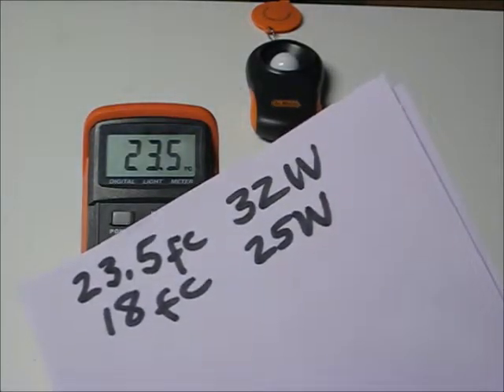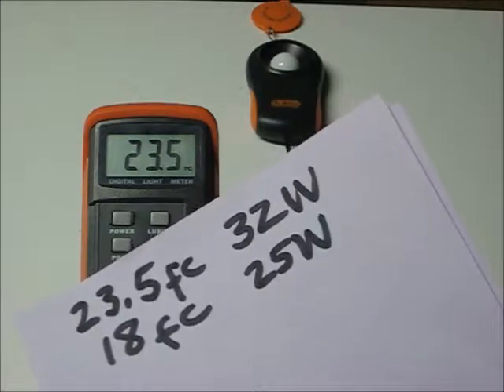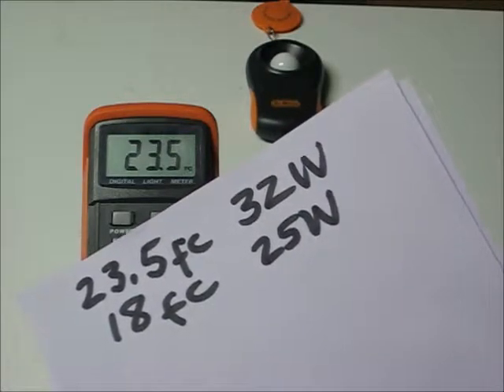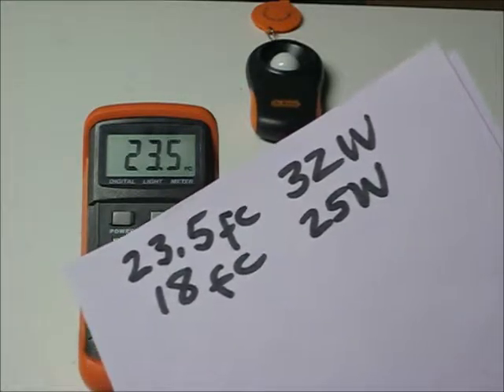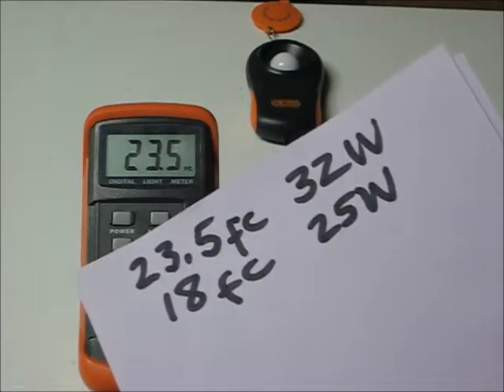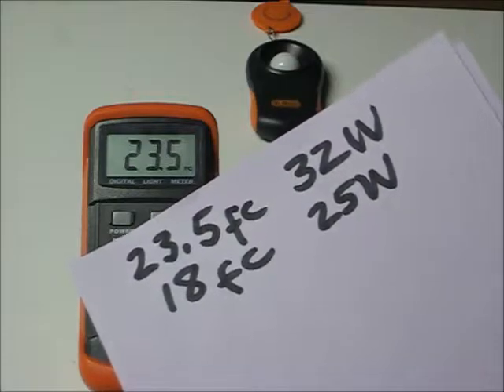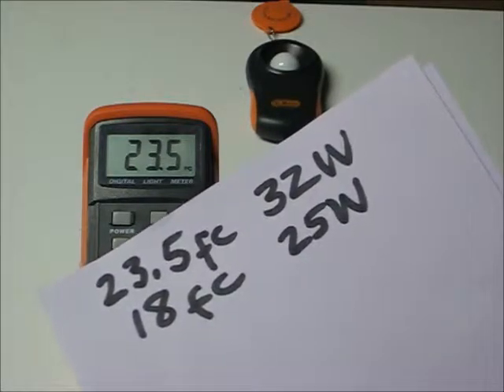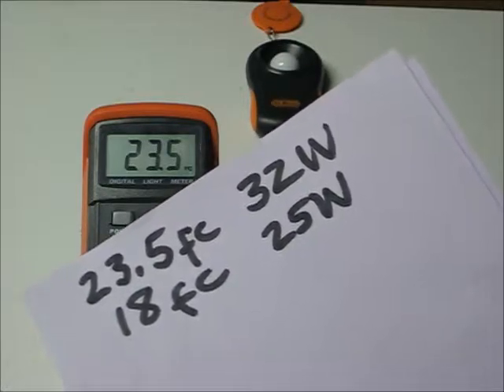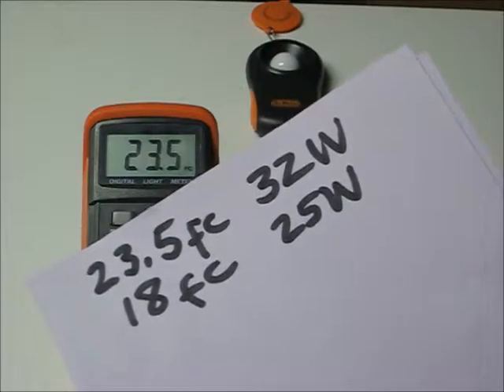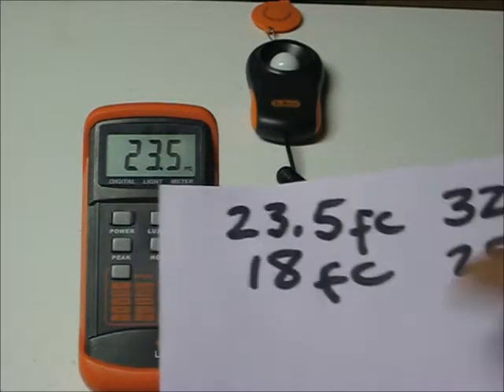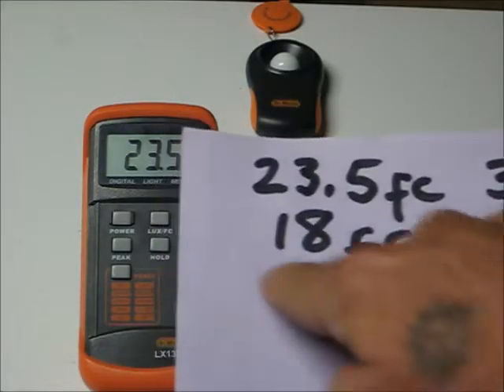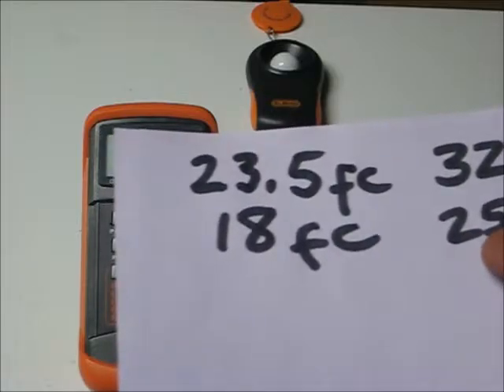I have 32-watt bulbs at 5,000K, and I have 25-watt bulbs at 4,100K. I figure that if I install the 25-watt bulbs, that will simulate this luminaire that we are using in the room becoming dim and yellowed due to age. We are going to set up a closed-loop daylighting controller. We want to bring the 32-watt bulbs down somewhat below 18 foot candles, because we know we should be able to get that out of the 25-watt bulbs.